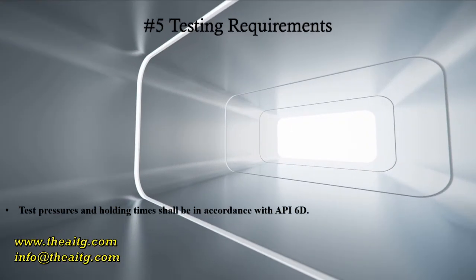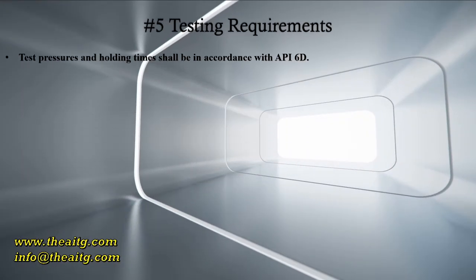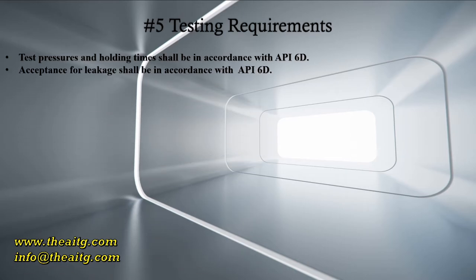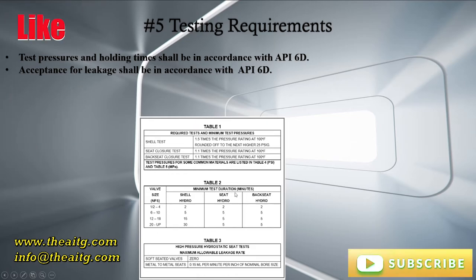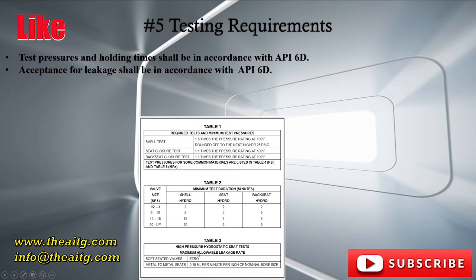Testing requirements: test pressures and holding time shall be in accordance with API 6D. Acceptance for leakage shall also be in accordance with API 6D. In these tables you can reference minimum test pressures, minimum test duration, and allowable leakage rates.